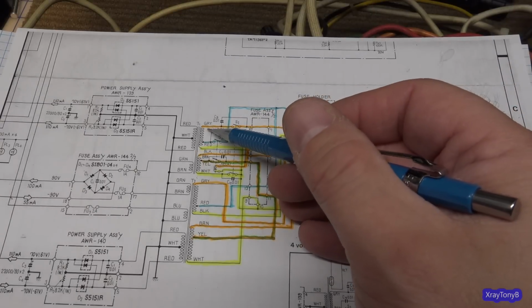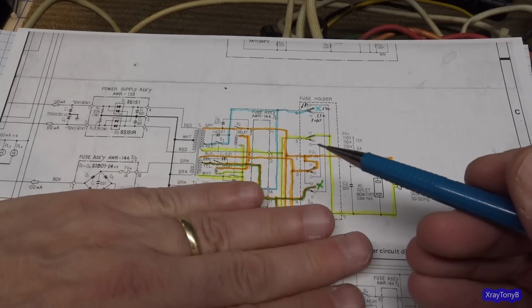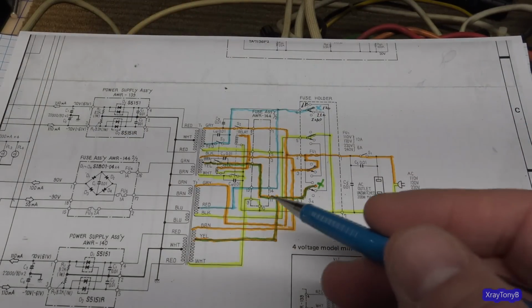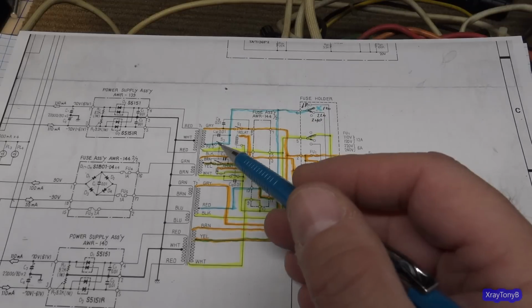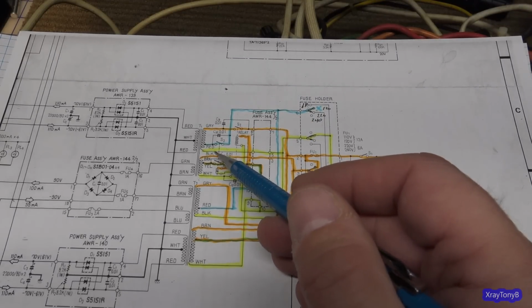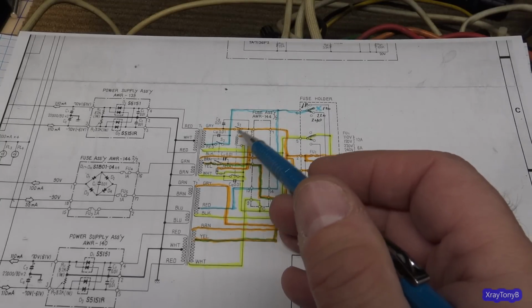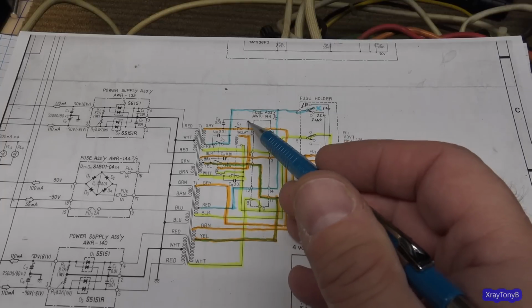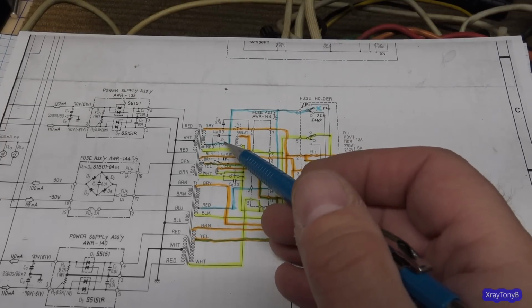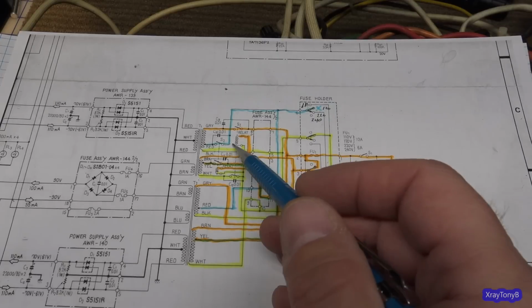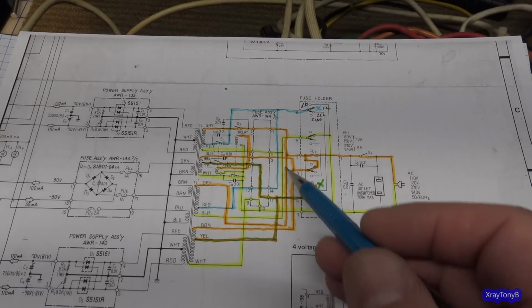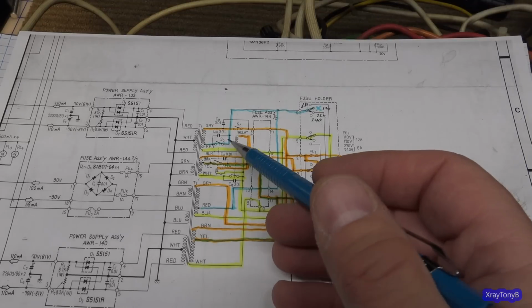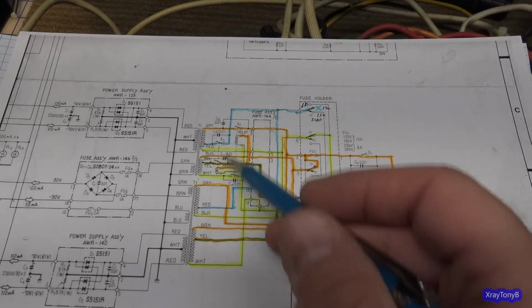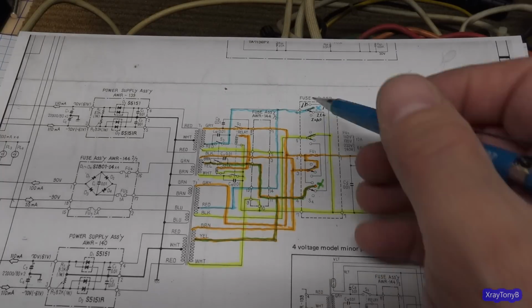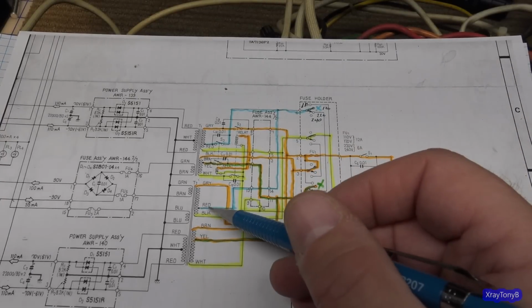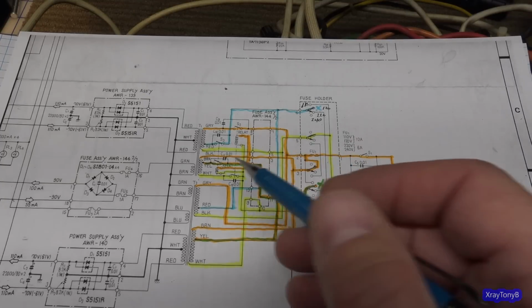It took me a minute to look at this. You have two separate transformers wired in parallel. Because you have a separate tap for 110 and for 120, they had to accommodate that by putting a relay on. Pretty much they just put relay contacts on everything. So when you have 120 volts, this relay contact is doing nothing. It's connecting these two leads together, but even though they're connected in parallel, there's no current flowing through here, because this isn't connected to anything. So essentially these two taps are kind of just floating, even though they're tied together.